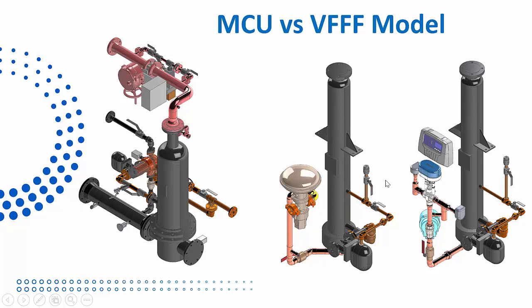There's two different options: mechanical, a self-contained mechanical blending valve on the water side. So no pneumatic, no electric, very easy install. Works on a differential pressure. As soon as someone opens a shower, a faucet, or a hose, it will create a pressure drop through the line and mix the right amount of very hot water with cold water to whatever set point you want. And of course, we have an electronic valve, BACnet, Modbus, whatever protocol communication you need.